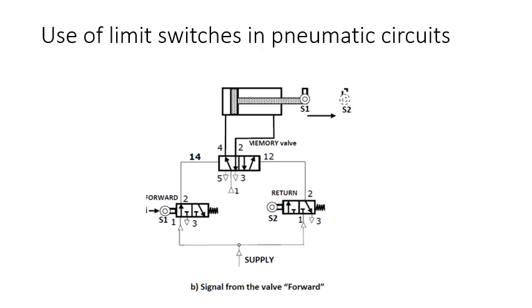The limit switches, we have two types. One is roller operated switches and the other is lever operated switches. In the roller operated type, we have a moving component that will move over the roller. While moving, it will actuate that particular valve, and the roller helps the moving component to move smoothly, right? When you have lever operated switches, the component will come and cause lever actuation. Only where we have stationary elements used to generate the signal, there we use the lever operated switches.